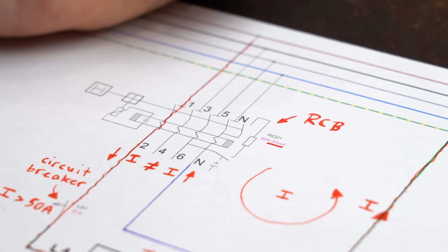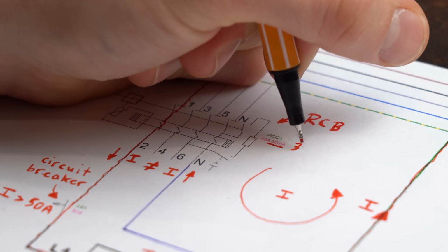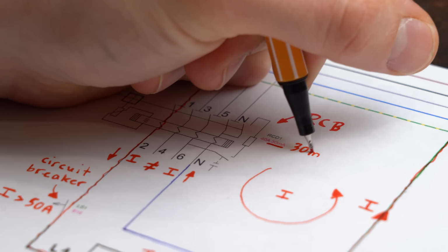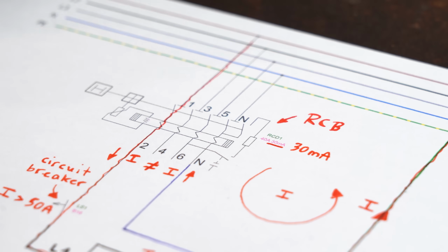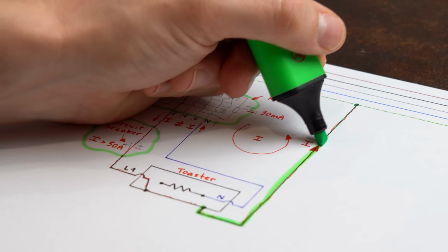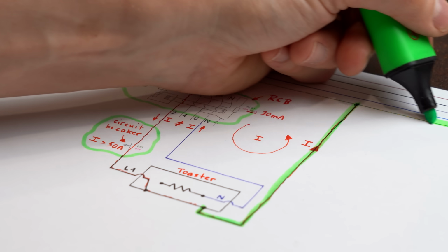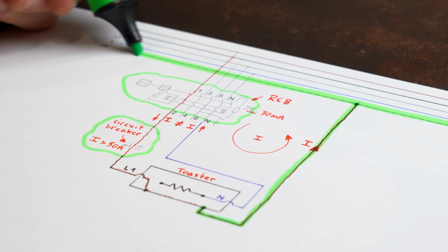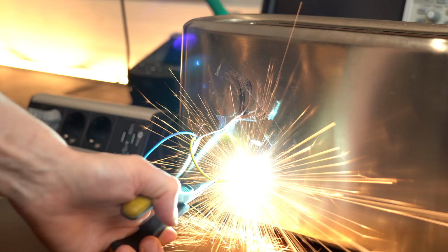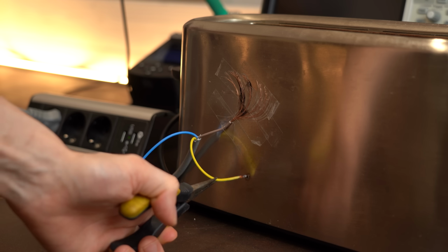Before this test I expected only the RCB to trip, because it requires way less current to activate. But hey, both protections would have saved my life in combination with the earth wire, meaning, summarized, its purpose in AC cables is that we do not get electrified.